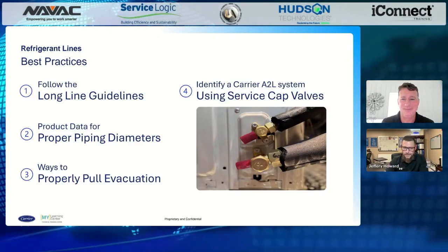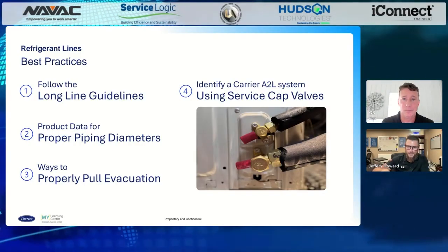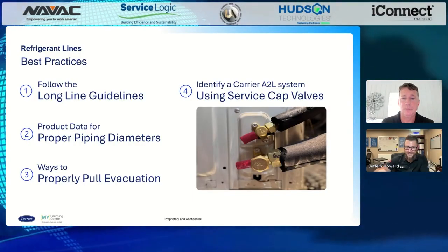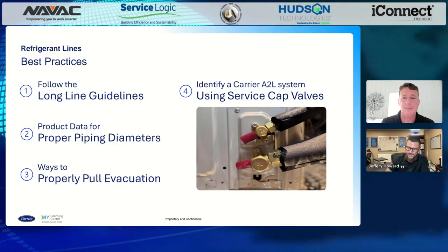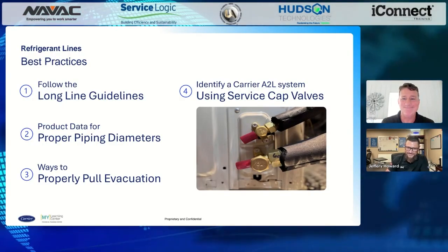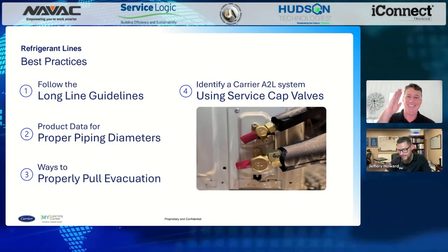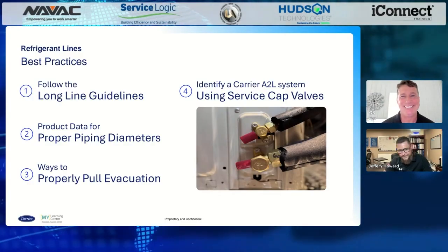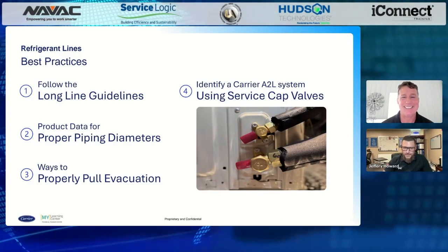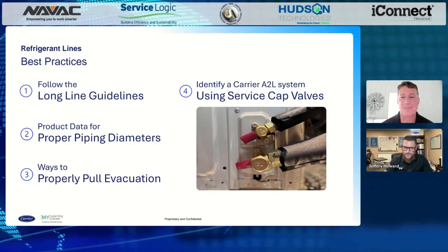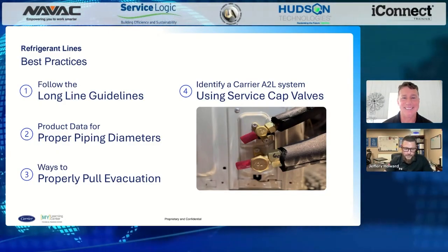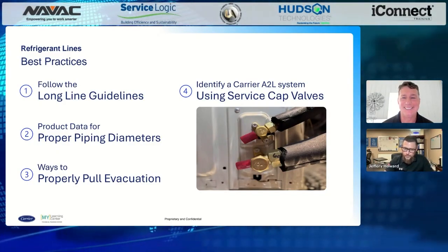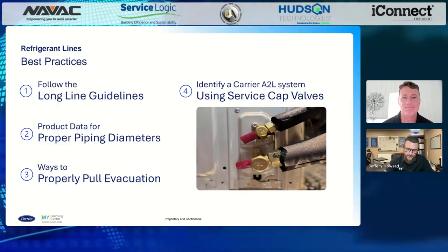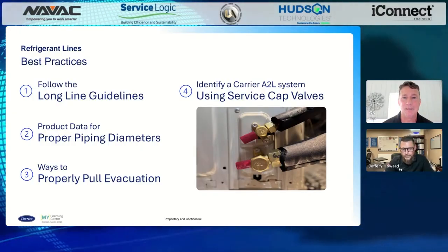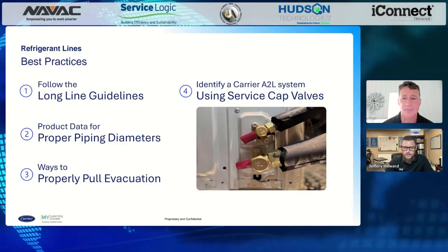You bet. And there's a lot of people that have put the micron gauge right on top of where they're pulling the vacuum. And what happens when you shut the vacuum off? You'll see your micron gauge climb, right? And as it starts to climb, you're like, I'm going to be here forever. Well, put it on the other side, hook up properly onto that portion, and then let it go. And if you use a large diameter hose directly to your vacuum pump, we've seen that it can actually make you more efficient in the field. And it's been 100% proven.